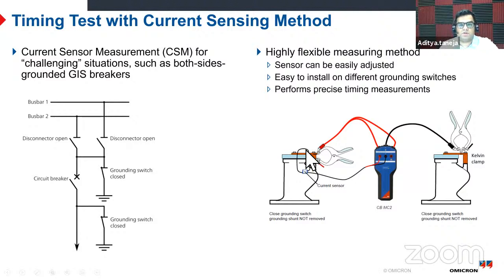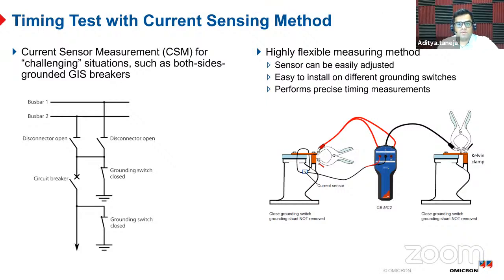the external ground switches which are coming, and this inductive loop will measure the current going through the ground, and it will only measure the change. So when the breaker opens or closes, the current through the ground changes, because when the breaker is closed, current is divided between the circuit breaker and the ground, and when the breaker is open, all the test current is routed through the ground.